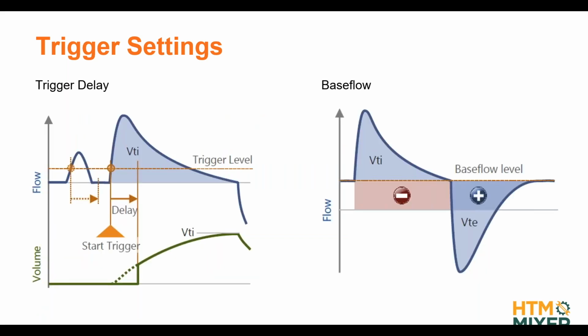All right, two more terms you might hear. They're not used very often, but for the sake of being complete, there's also a setting called trigger delay. This can be used if you have signal spikes above your trigger level and you don't want to consider them as triggers. Then you can set a trigger delay, and this specifies for how long the trigger condition needs to be true until it's really considered an actual trigger. It is kind of important in high frequency ventilation, for example. If you have your default settings and the delay is a little bit too long, you might miss some pulses in the high frequency ventilation that you're measuring.